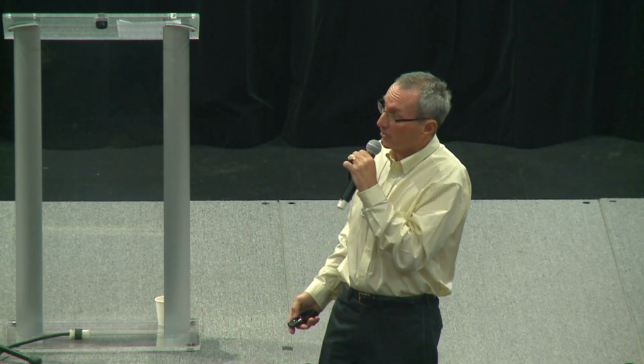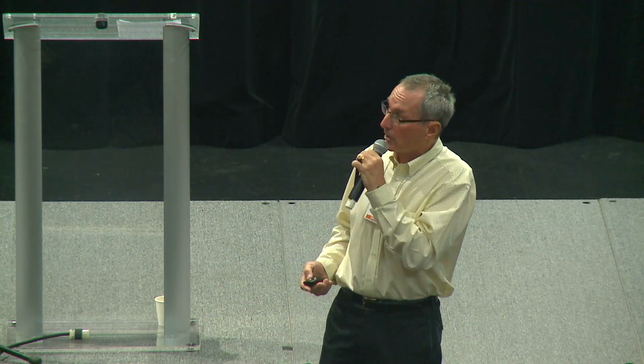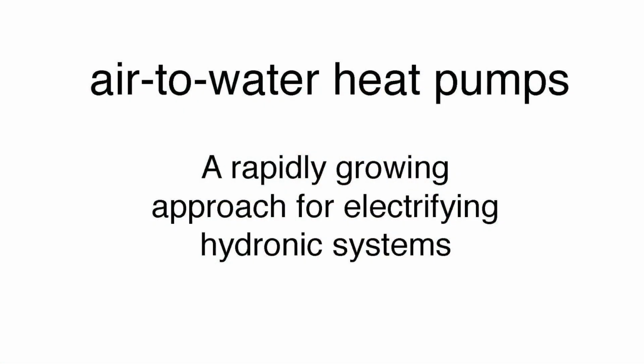So imagine a house full of south-facing glass with a 6-inch concrete slab. The comfort is not going to be there because the slab's always going to be overshooting in the morning and probably undershooting in the evening. So low thermal mass tends to be better for low energy buildings. Air to water. We've got several air-to-water heat pumps here. I'm delighted to see that. This is a product category that I think is going to become very important in the hydronics market. I think eventually this could eclipse geothermal in terms of numbers because it goes in without the earth loop, and that's a huge savings.